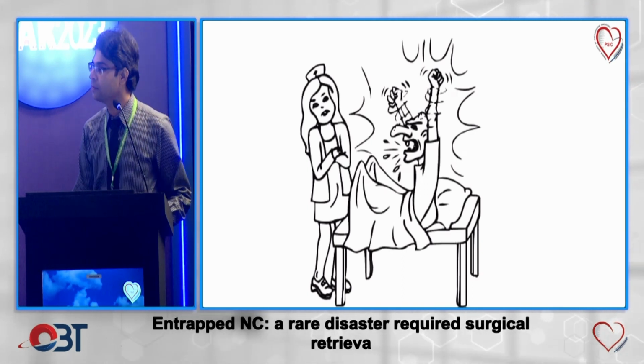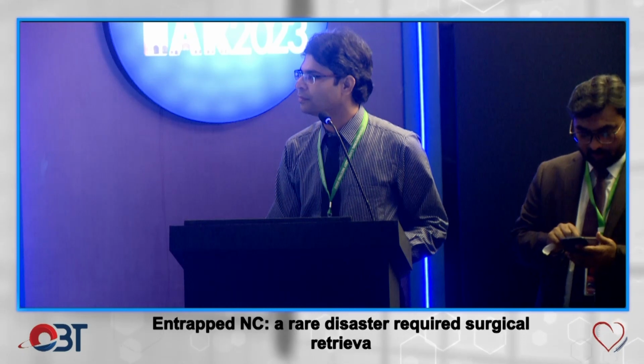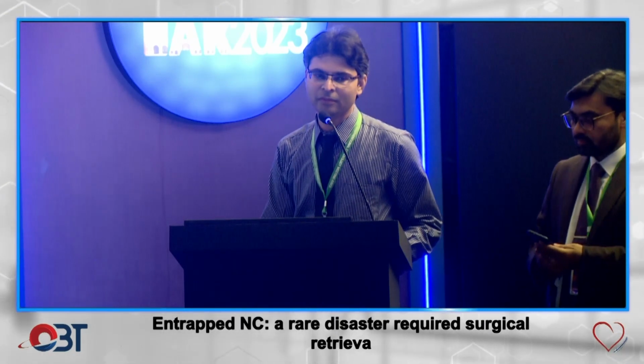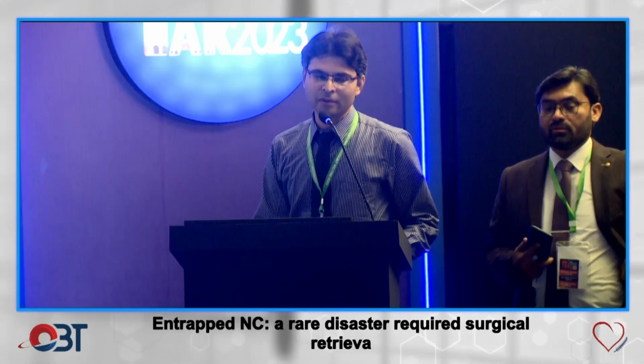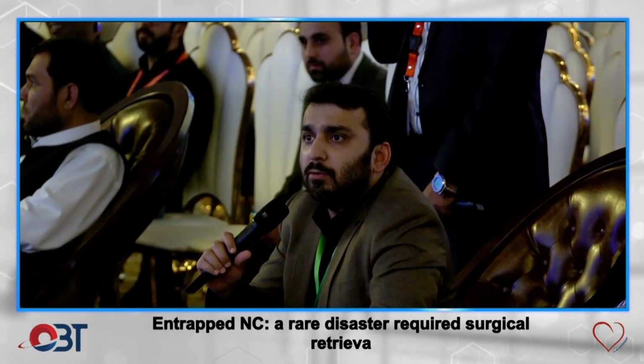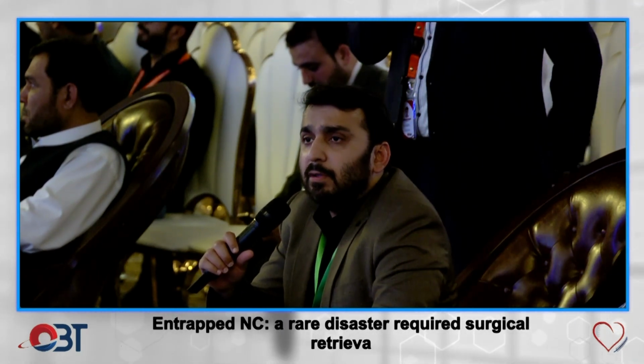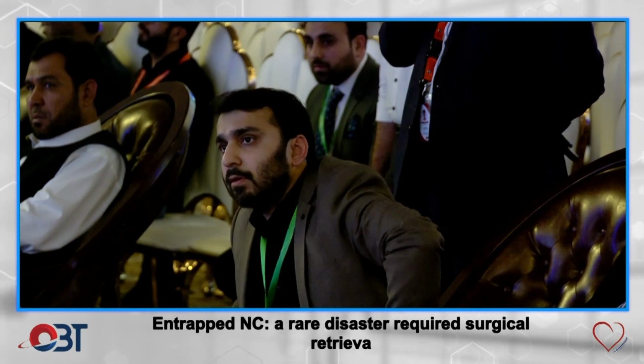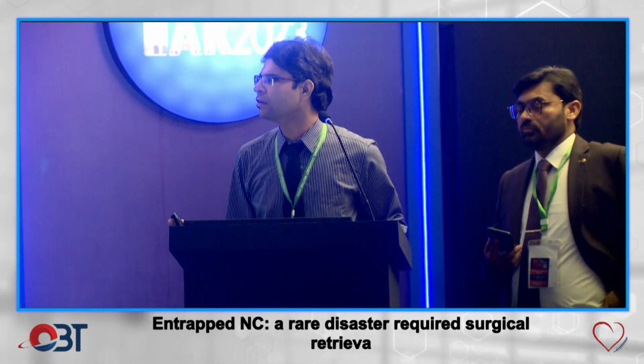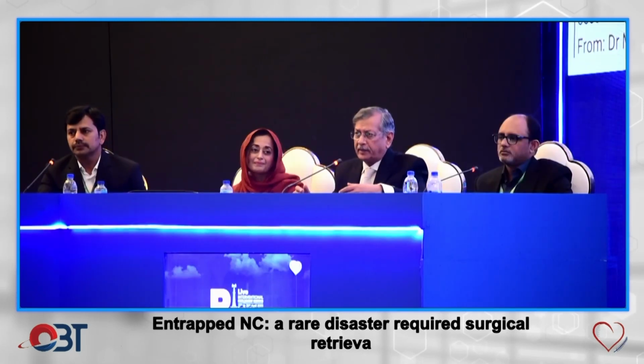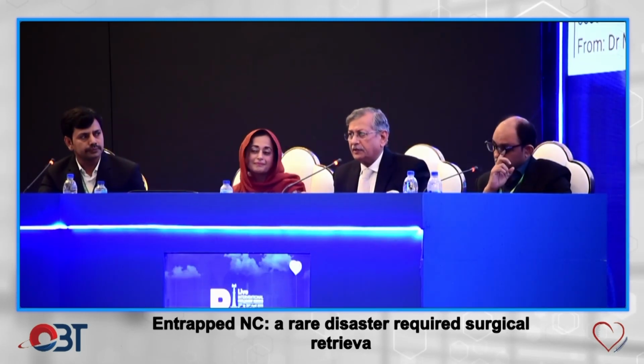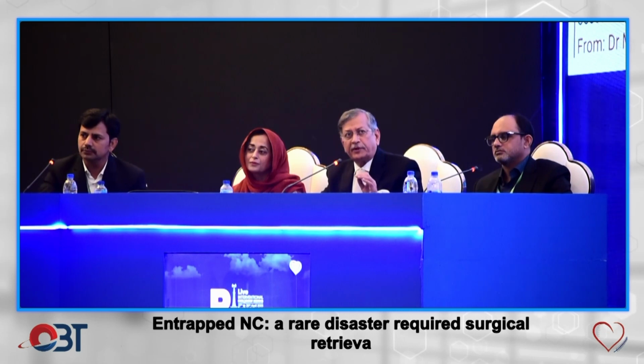And my last question to you is, what is the commonest cause of this balloon not being deflated? The proportion of the dye and saline is not okay. Maybe. Shaft kink. It is a common cause. Whenever you retrieve the shaft, look at the shaft. Usually there is a shaft fracture. When you suck, the negative pressure does not reach the balloon. Always look for it.